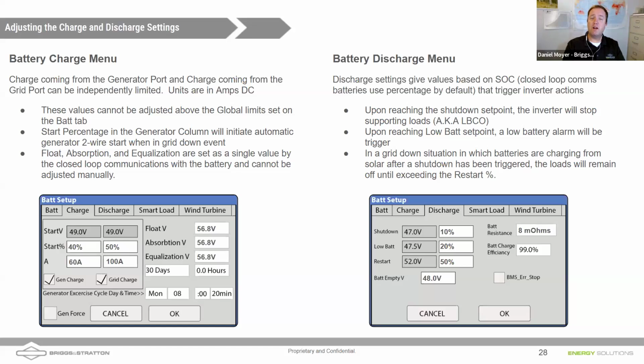Now, Nathan, what happens if it stays off until you hit that restart percentage? If you don't have grid, right? If grid's not available, if there's no AC power source, those batteries will continue to charge and the loads will stay off until you hit that restart percentage. I'd probably move that down a little bit, maybe to 30 or 40%. You do want to have it above your low battery. It has to be above your low battery value. And you want to make sure to let those batteries charge for a little bit.